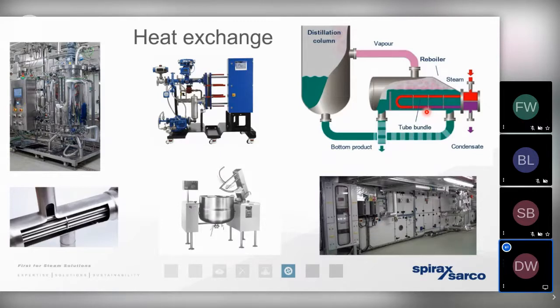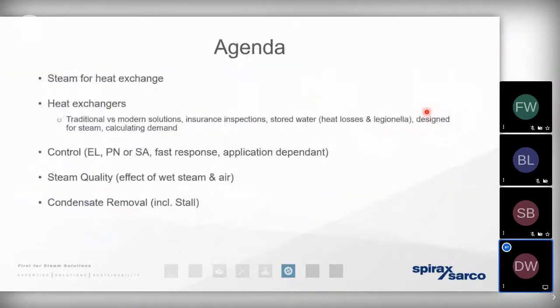And as you can see on the screen, heat exchangers, well, that terminology can cover a huge range and variety of different capital equipment, such as shell and tube heat exchangers, plate heat exchangers. It can be process capital equipment such as jacketed vessels, bioreactors, coils in air handling units, or even reboilers in the oil and gas industry. So in today's presentation, we're going to look at why steam is so popular in so many different heat transfer applications. And we're also going to look at the considerations that we need to give to steam that are completely different to other sources of heat energy, such as low temperature hot water, for example. And then we're also going to look at other issues that are unique to steam heat exchangers, such as stall and condensate removal.